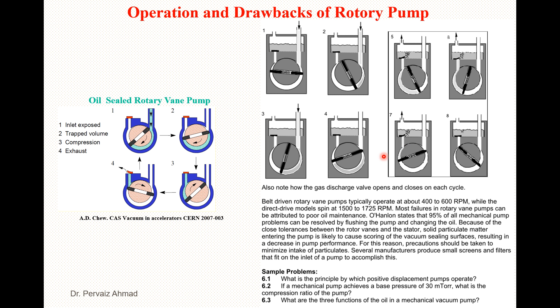Belt-driven rotary vane pumps typically operate at about 400 to 600 revolutions per minute, while direct-driven models spin at 1500 to 1725 revolutions per minute. Most failures in the rotary vane pump can be attributed to poor oil maintenance — this is one of the main drawbacks since the rotary pump uses oil.